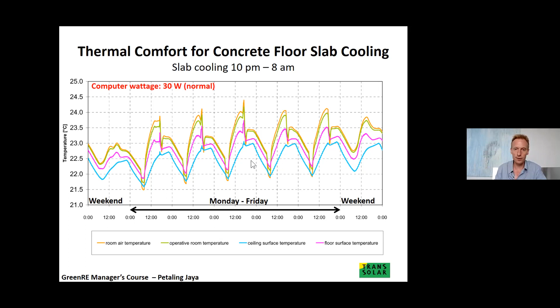And the other advantage of doing this is that when you feed 18-degree water into the slab, the lift of your chiller is much reduced, because you don't have to cool water down to about 6 or 7 degrees, which is a typical chilled water supply temperature. So often we would be down here delivering about 6-degree water.